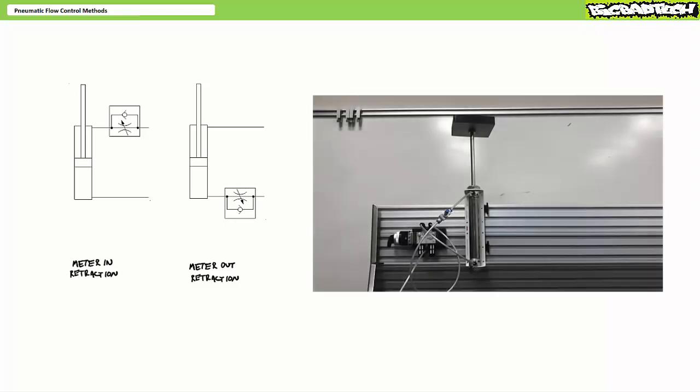Consider a vertically mounted pneumatic cylinder that lifts on extension and lowers on retraction. Extension is not an issue. Either meter in or meter out extension method work equally well. Retraction however, that's the issue.